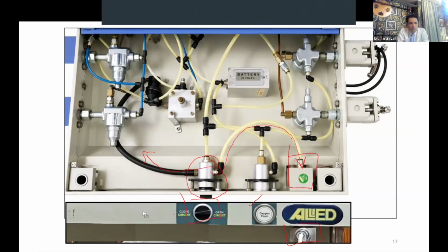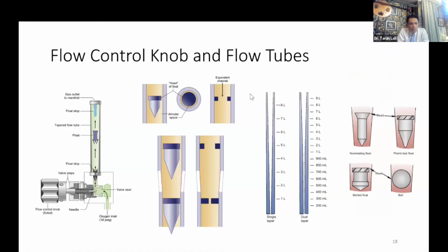Now, if we go back to what we saw in the book diagrams, till somewhere here, minus the output, this part is your high pressure system. Then with the outputs, everything else that you see on the tray is the intermediate pressure system. Beyond the intermediate pressure system, what we see on the outside is your low pressure system. In the low pressure system, what is important is your flow control knob and the flow tubes.